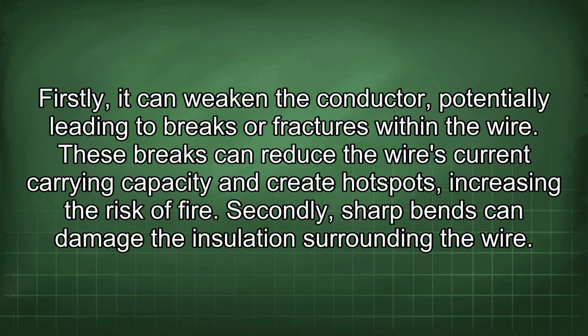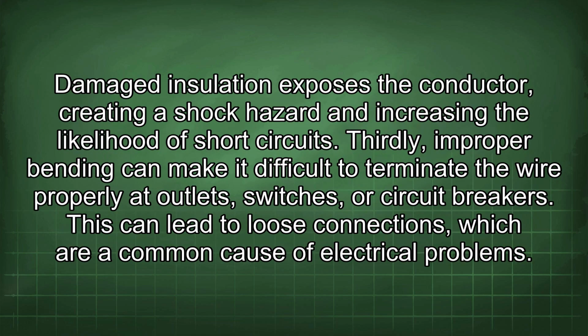Secondly, sharp bends can damage the insulation surrounding the wire. Damaged insulation exposes the conductor, creating a shock hazard and increasing the likelihood of short circuits. Thirdly, improper bending can make it difficult to terminate the wire properly at outlets, switches, or circuit breakers. This can lead to loose connections, which are a common cause of electrical problems.